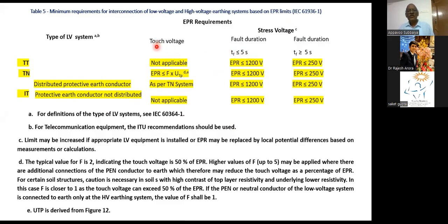Because these touch voltages, for example in TT, are not applicable. In TN, it is applicable, depending upon the integrity of the supplier's earthing system, which is denoted by F, which in turn depends upon the PEN conductor earthing. So this meticulous thing, please take it as your homework. What I can say is, in the supplier-fed distribution system or your own substation transformer, adopt these two things.